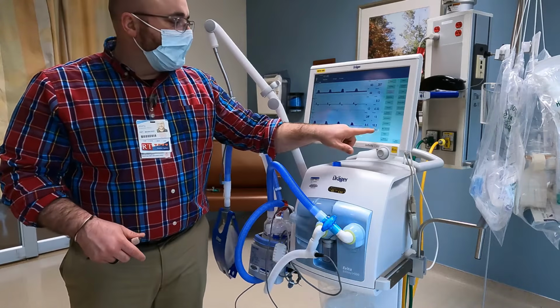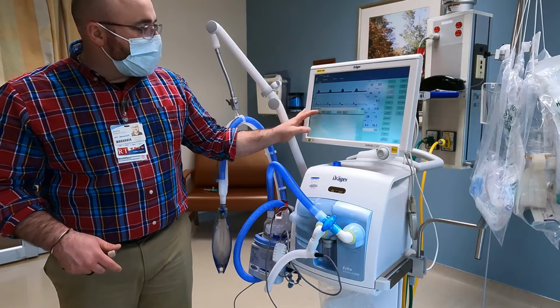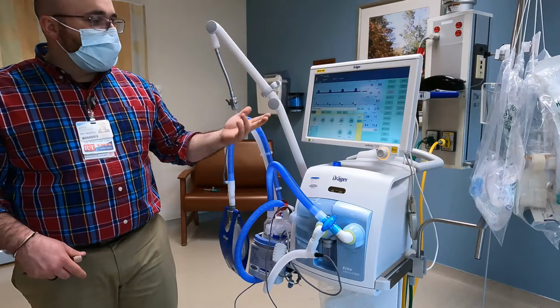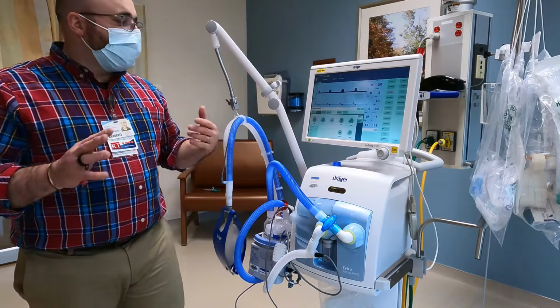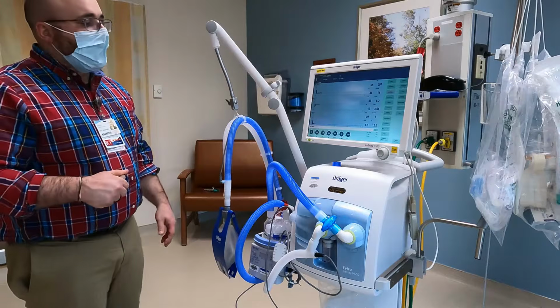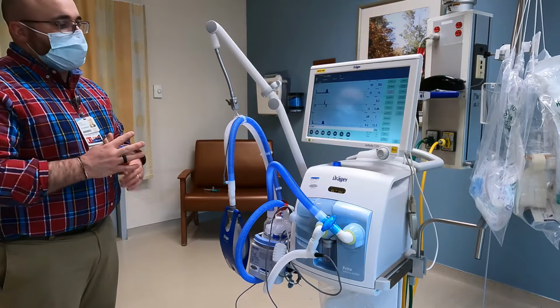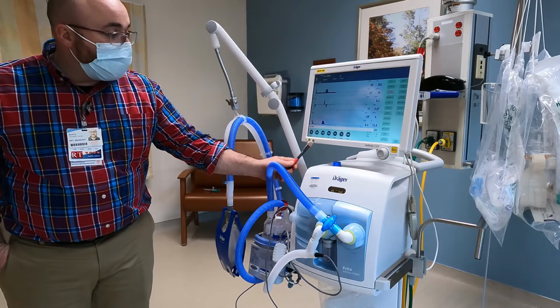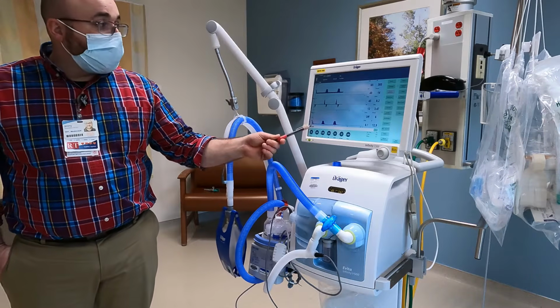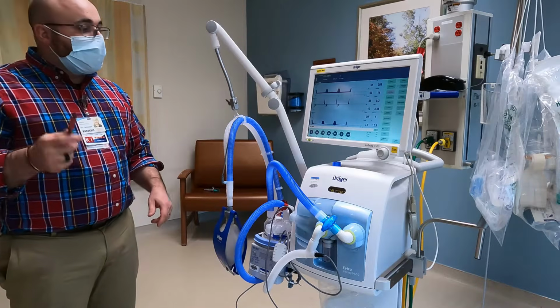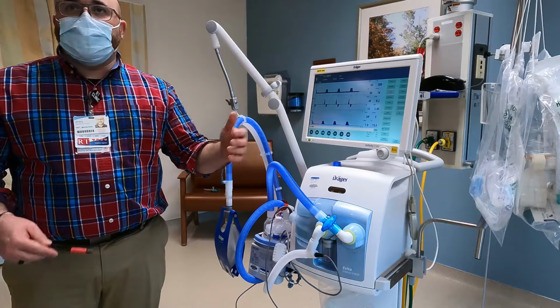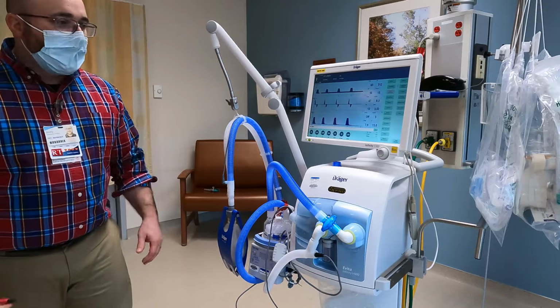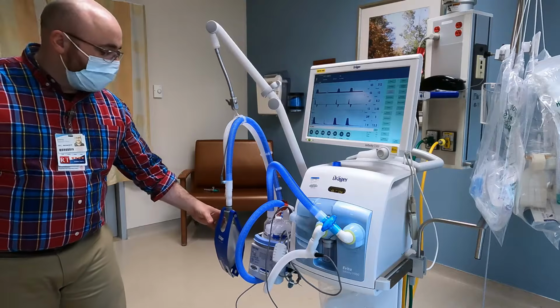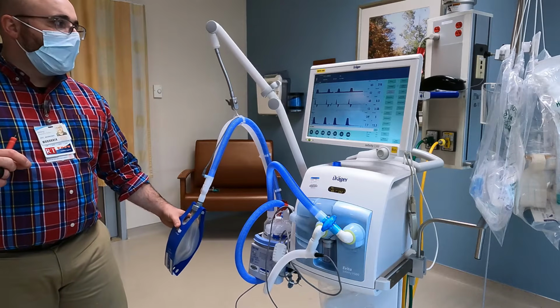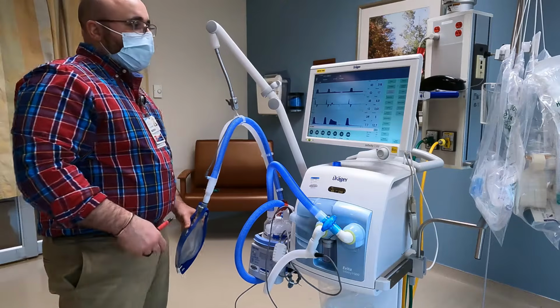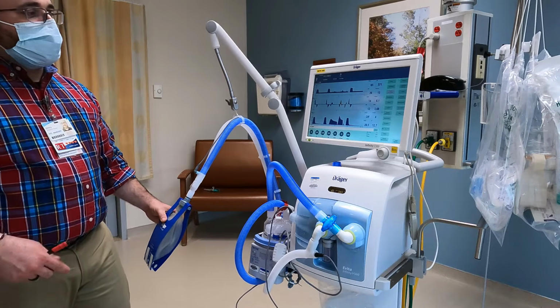The next mode I'll show you is VCSIMV, so synchronized intermittent mandatory ventilation. You don't need to remember it, just remember it's kind of a middle ground. So in SIMV, the generic aspect of it is we're going to give them 12 550s per minute, this says 330 but it would be 550. If they take their own breath though, we are not going to give them 550. We're going to give them help, what we call pressure support. So we're going to support their breath a little bit. We're not going to finish it though. They've got to do a little bit of work. So you can see that volume is not quite as big. And you can see now we have these little gray ones on the flow.